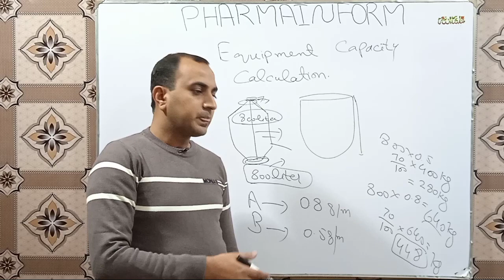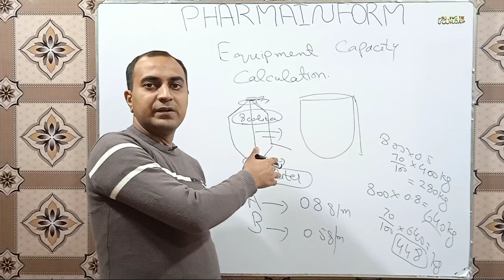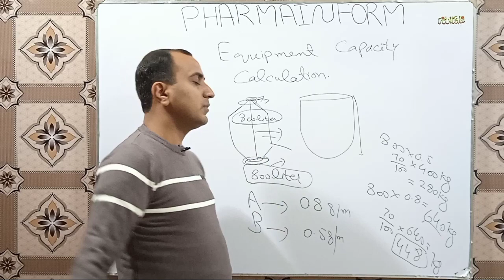And it may be a hectic activity, so you can use another method, which is you can take a container, suppose 25 liters, add water into it and calculate the time for its filling. From this calculation you can take the time required for filling of this blender, and from those values taken for the 25-liter container, a conversion value is used, and you can calculate the capacity or water filled into the double cone blender.